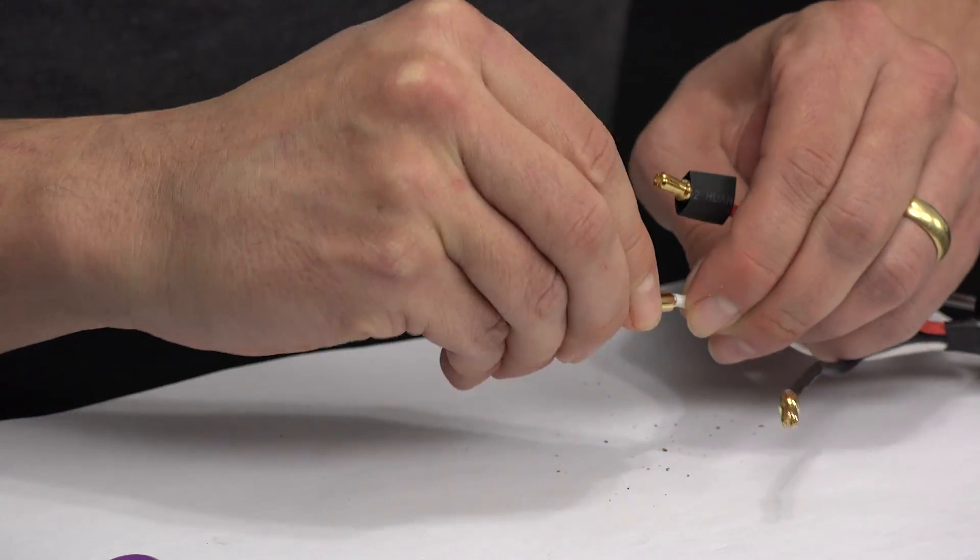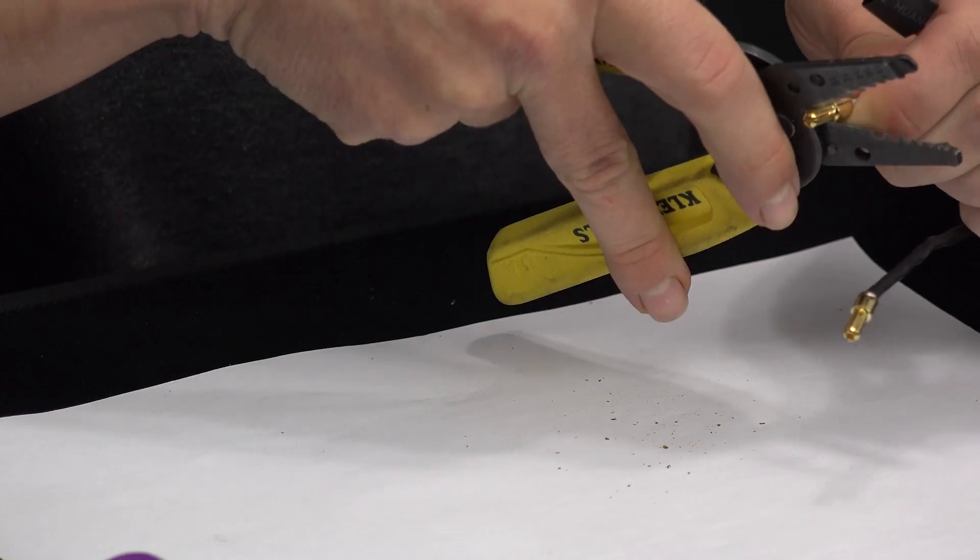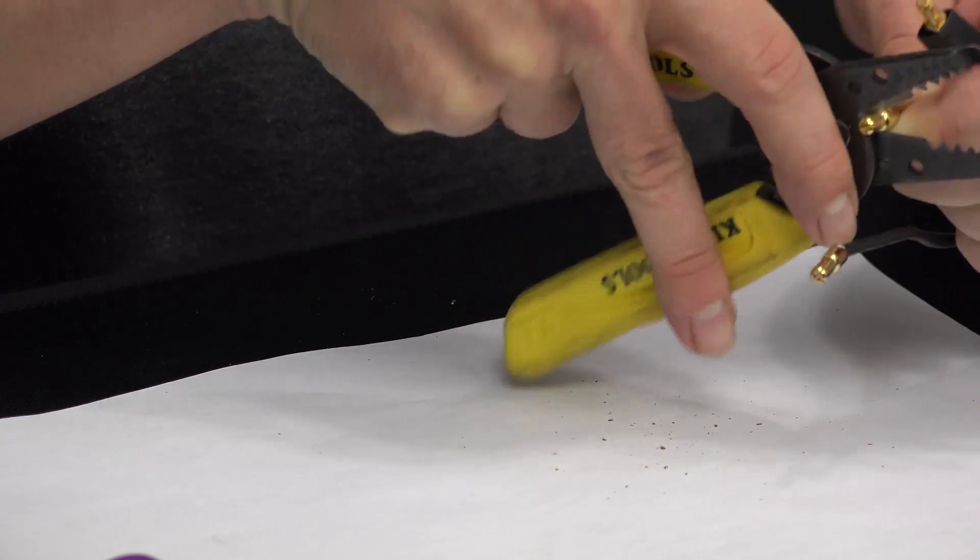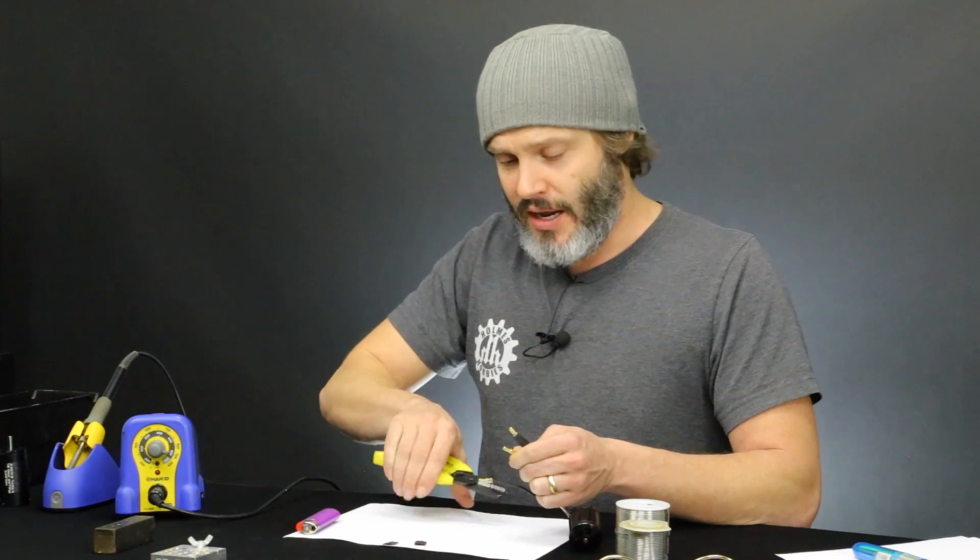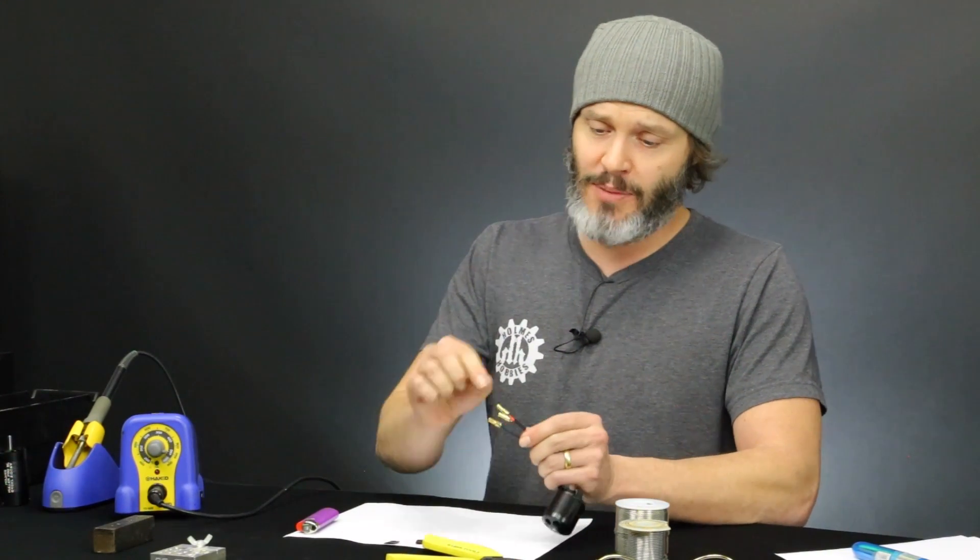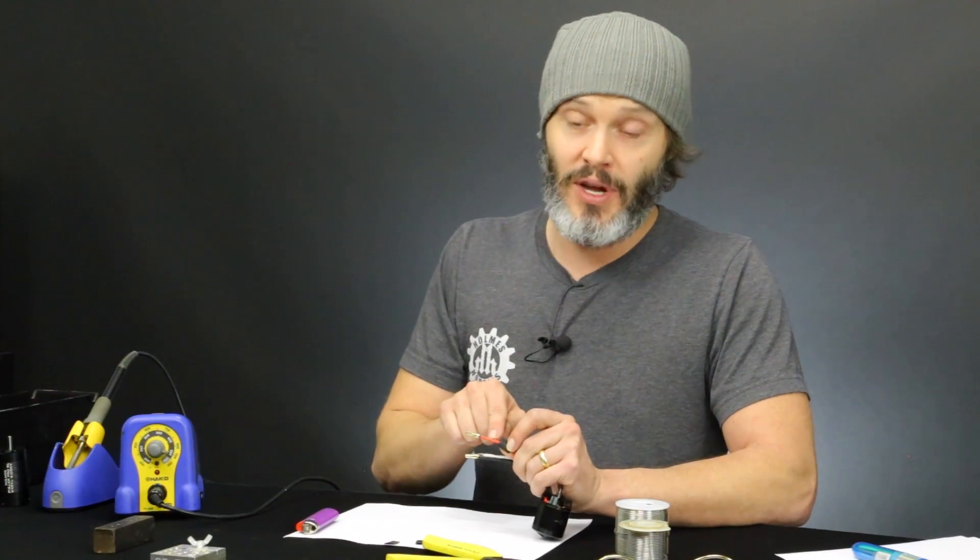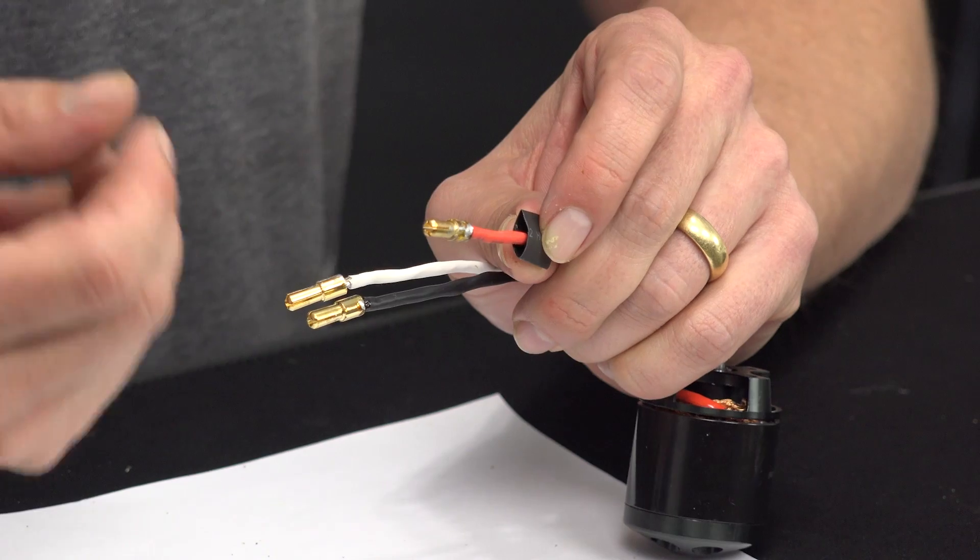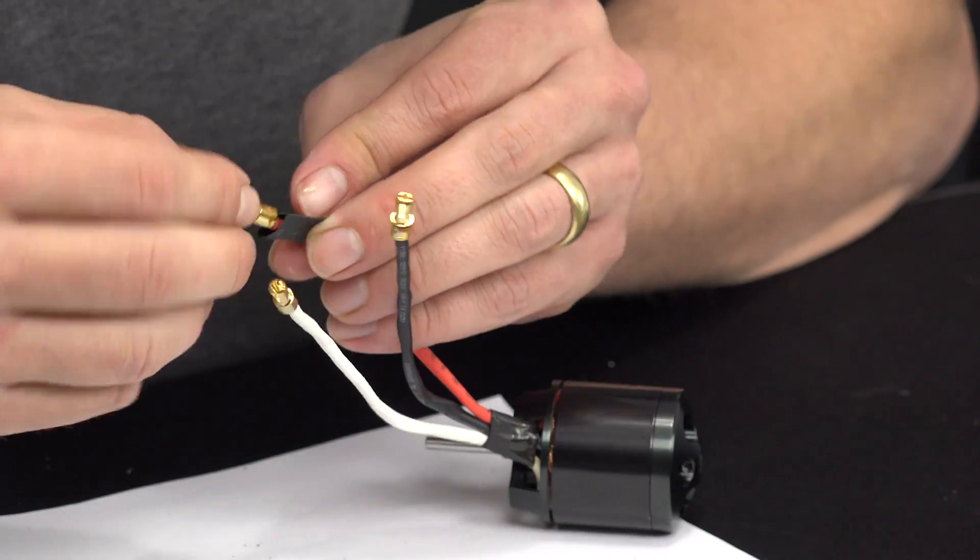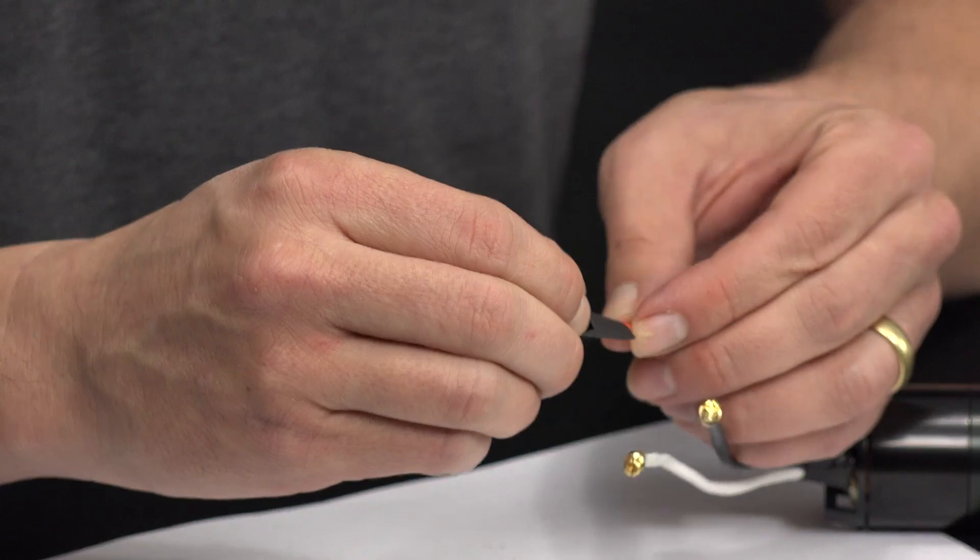And as you can see, we're getting a lot of the flux onto the table. So, which another thing I should mention, do not use acid flux on electrical connections. If you have the ability to clean every bit of that flux off, then it would be okay. But an acid flux will corrode over time. If you have a multi-strand wire, it's going to soak up into that wire and it will corrode that wire over time and you give it enough time and it'll just simply break the wire. I've seen it happen. For example, if I did acid flux on this instead of normal rosin flux, it would soak the flux up into the wire, down the wire, and then wherever it would stop, then over time that would start to corrode and get eaten up, so to speak. And with the flexing over time, it would break right there and just separate. So do not use acid flux on electrical connections unless you think you can totally get it clean. Unless it's a single wire going onto a single object, you can't. If it's got a multi-strand wire, you will not be able to clean it.